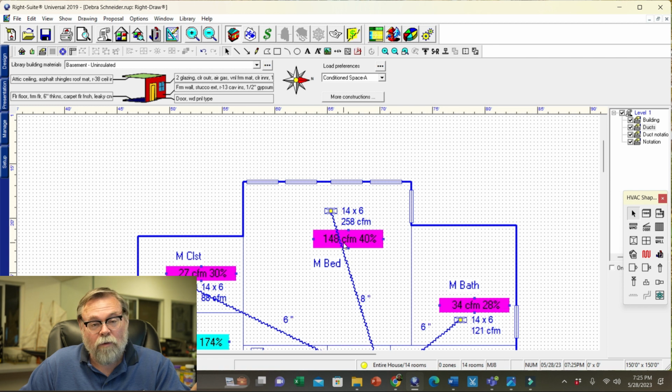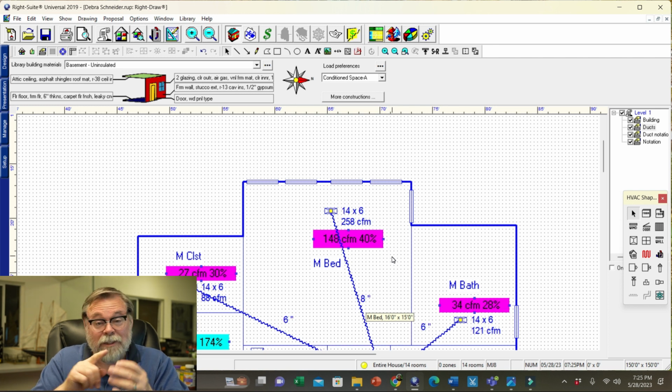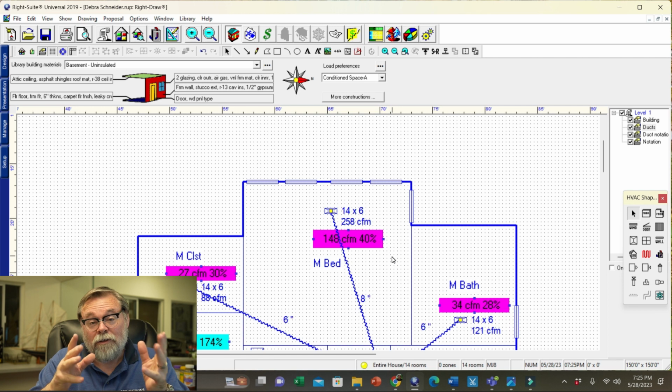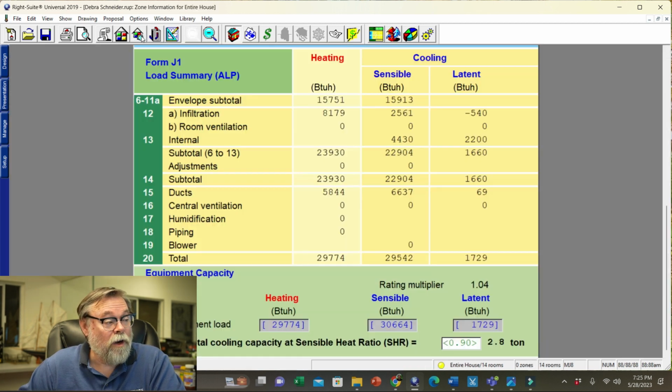And now it's down to an 8-inch duct again. It was the same as if we rotated the house. So we did a what if, so she could see that she could get by. Putting those sunscreens is going to improve the temperature in the room, make that room more comfortable. And let's see what it did to her tonnage.